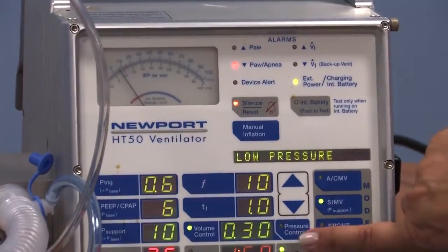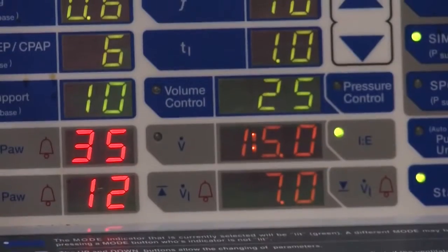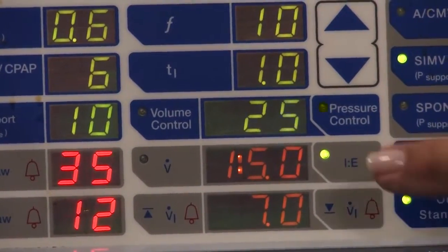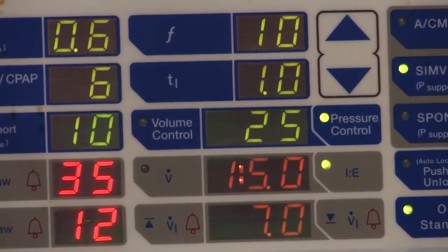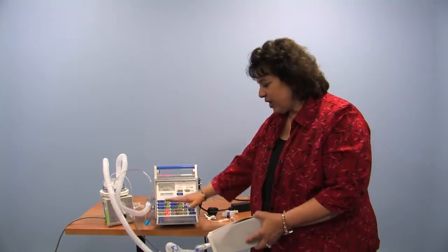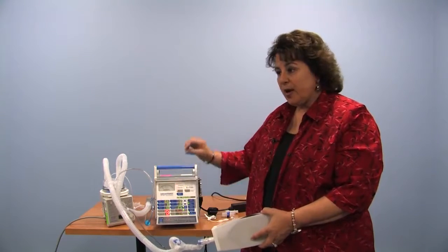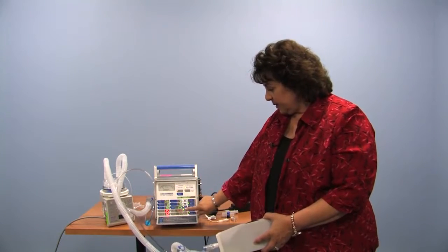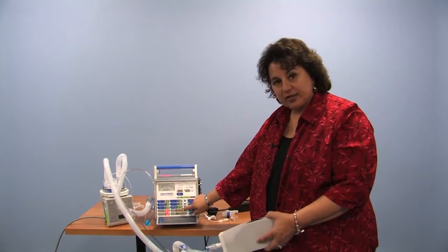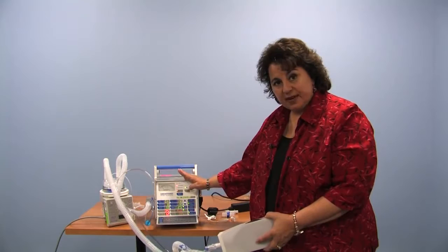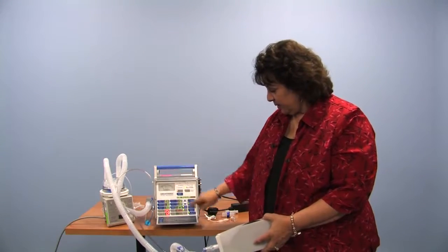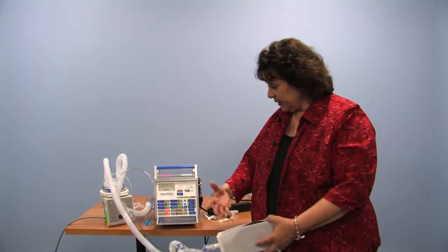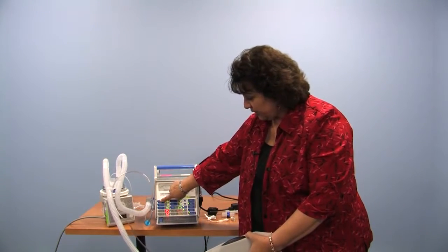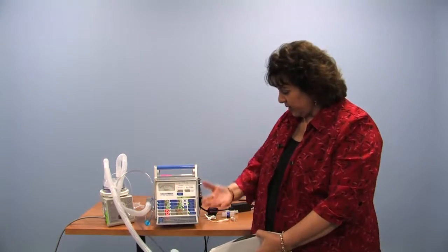What I'm going to do now is push this pressure control button. I hit it once. It tells me that the peak inspiratory pressure is set for 25. I'm going to hit it again to change it. So now we've changed our ventilator settings to pressure control, or pressure targeted mandatory ventilation, and pressure support. That means that 10 times a minute, our patient now will have a breath delivered that achieves a pressure of 25 centimeters of water, and we can see that here as well. It'll inhale for 1 second and then release. If I initiate breaths, you'll see the trigger light go off. So that tells me that I'm initiating breaths and it's firing.